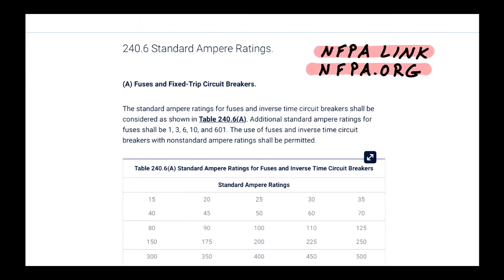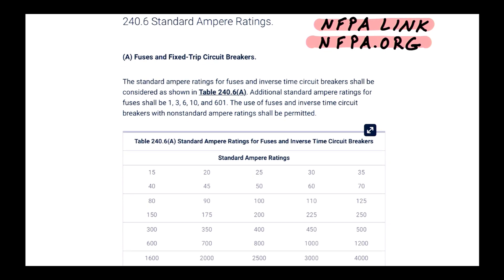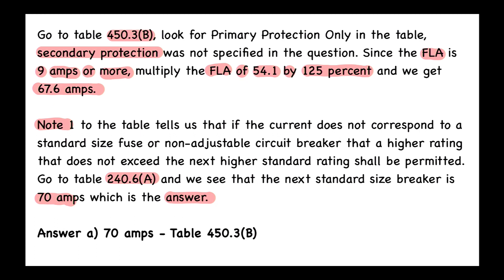Table 240.6(A) confirms that the next standard size above 67.6 amps is 70 amps. So the answer to this question is A — 70 amps. We covered transformer electrical theory, the PIE formula for both primary and secondary sides, and two key tables: Table 450.3(B) and Table 240.6(A). The reference is Table 450.3(B).